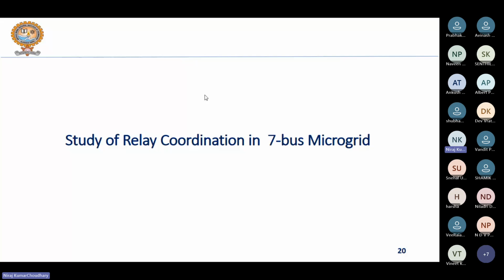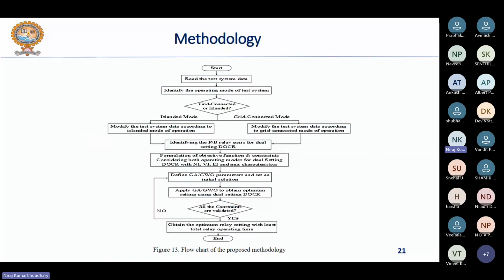Now, the next part of this presentation is related to some of the basic results that I will show you, and these are basically related to the theory part. Just as we have discussed, that is the impact of the mode of operation of the microgrid as well as the impact of different types of relay characteristics. I will not go into that much detail of this flow chart. You just need to do one thing: first of all, identify the mode of operation of the microgrid, that is whether the system is operating in the grid connected mode or in the islanded mode, and accordingly modify your system data for the preparation of the primary and backup relay pairs for maybe conventional DOCR or dual setting DOCR.